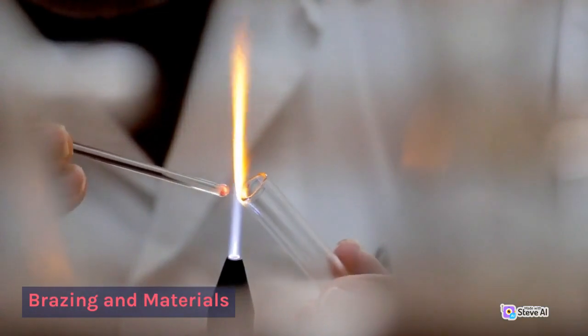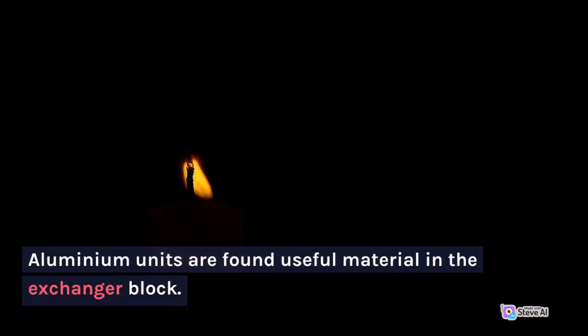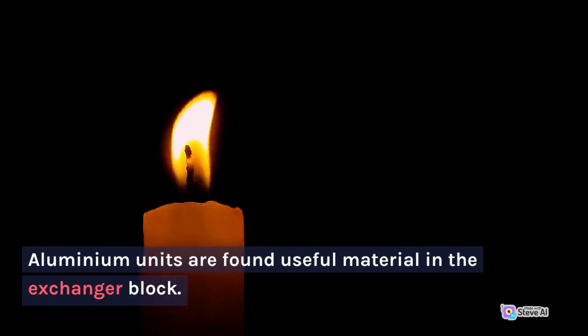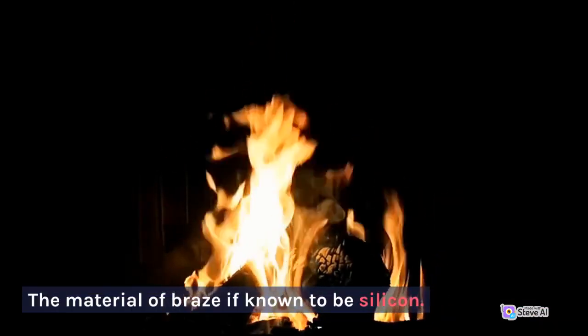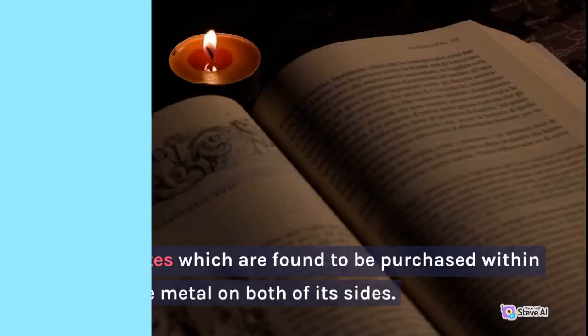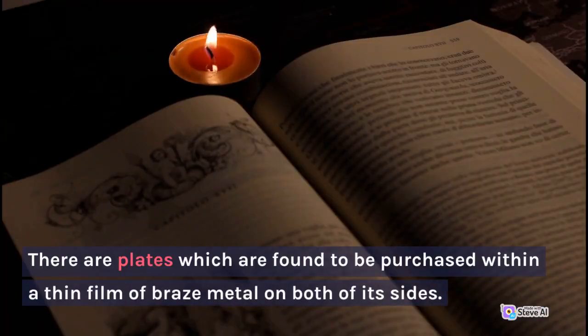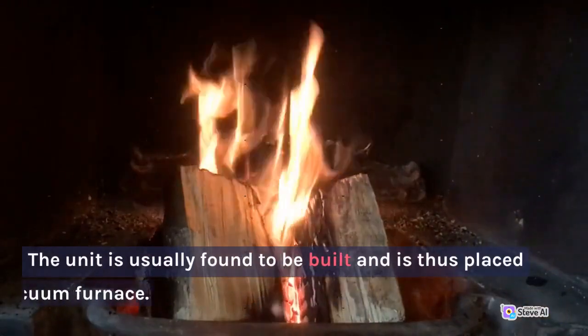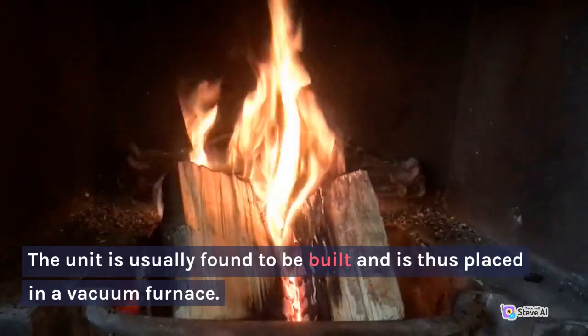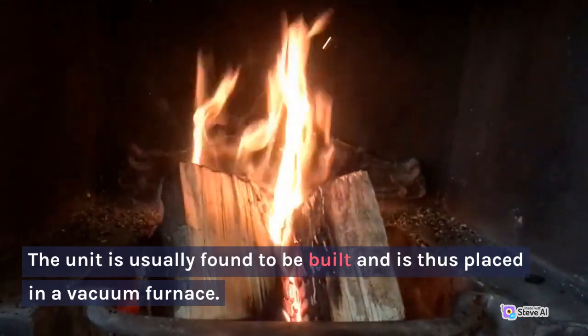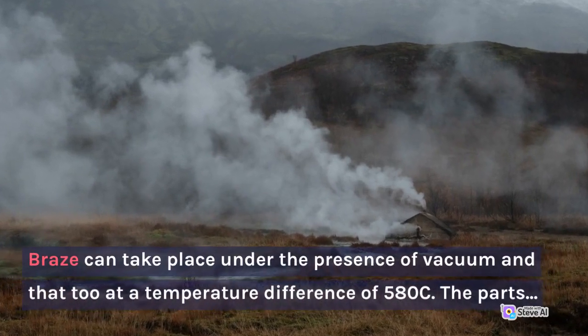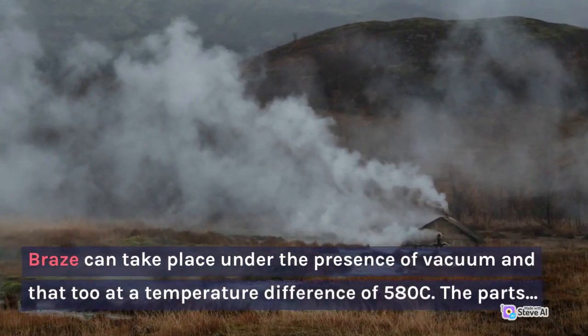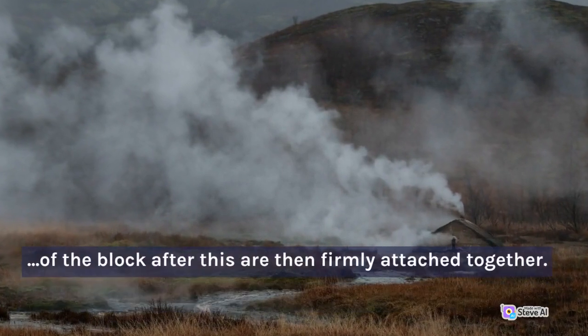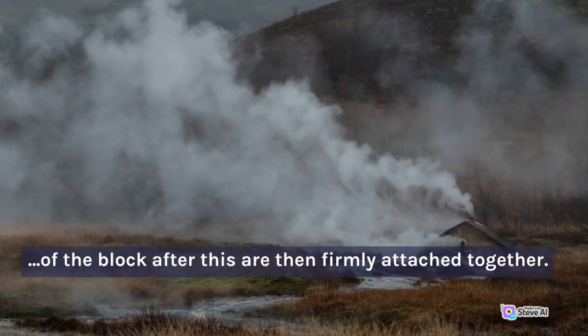Brazing and materials. Aluminium is a useful material for the exchanger block. The braze material is silicon. The plates are purchased with a thin film of brazing metal on both sides. The unit is built and placed in a vacuum furnace. Brazing takes place under vacuum at a temperature of 580 C. The parts of the block are then firmly attached together.